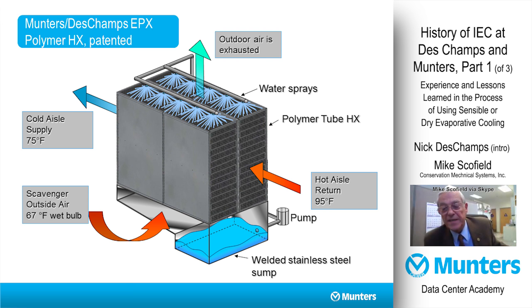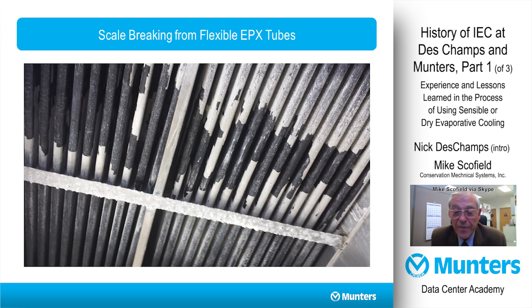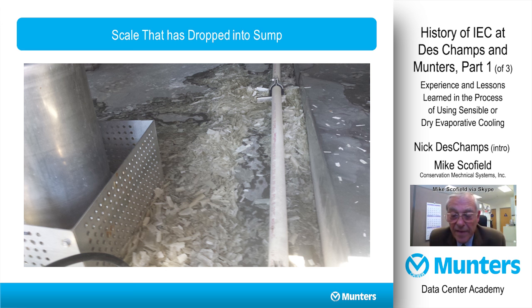We've taken the design from a vertical to a horizontal application, where we have found that the ability of the tubes flexing during fan startup causes a self-cleaning of the heat exchanger surface and the removal of water hardness from the wet side surface after the buildup gets to a certain mill thickness. The tubes flexing, shaking during fan startup successfully shed the surface and allow the heat exchanger to work at as new effectiveness.